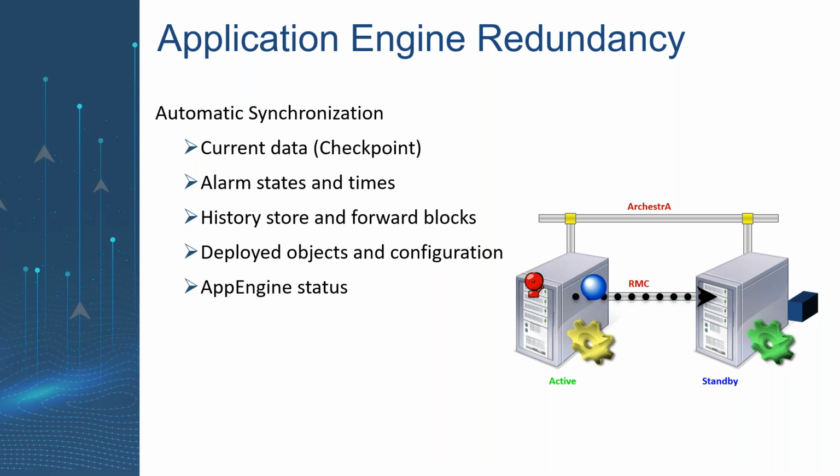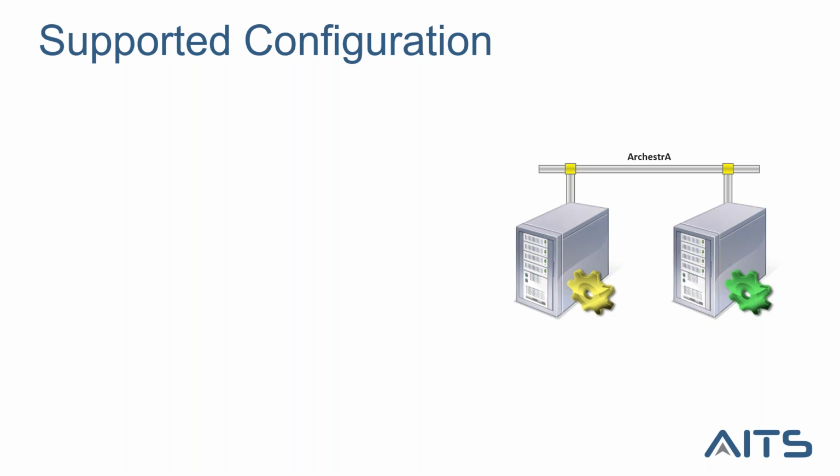This type of data might make some traffic on the network. This is why the RMC network must be separated, peer-to-peer. In this case, you have two network cards on every PC. The first and highest priority is the application, and the RMC has second priority. This is how it's supposed to be configured, and this is how you must keep it in mind: different networks, different subnets, totally separated, different switch. This is our recommendation.